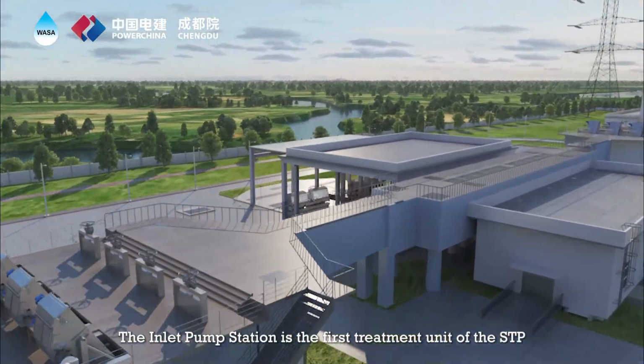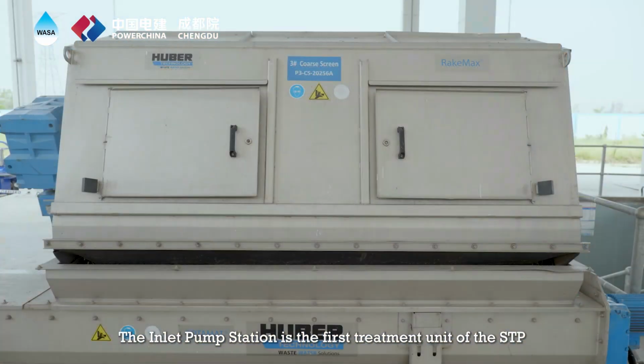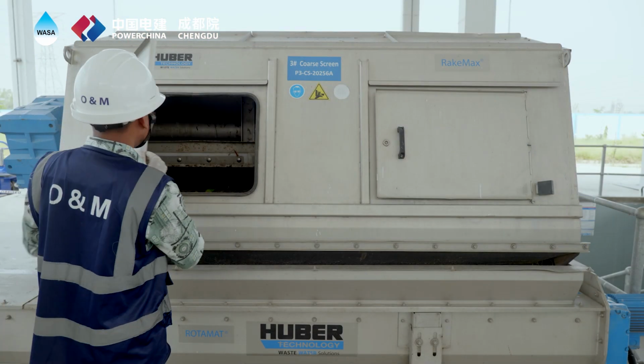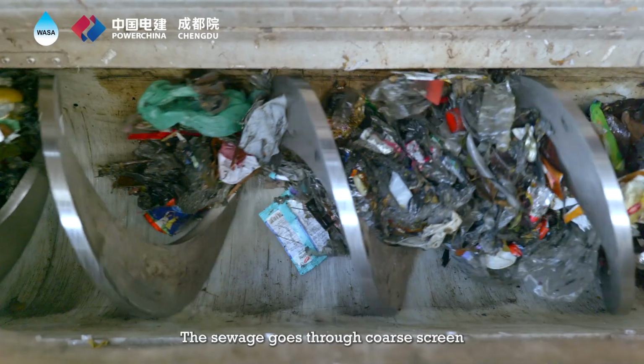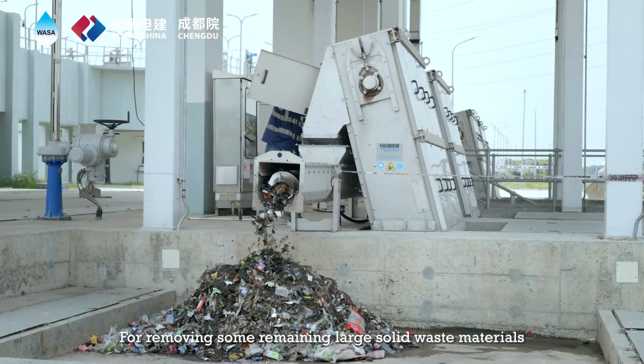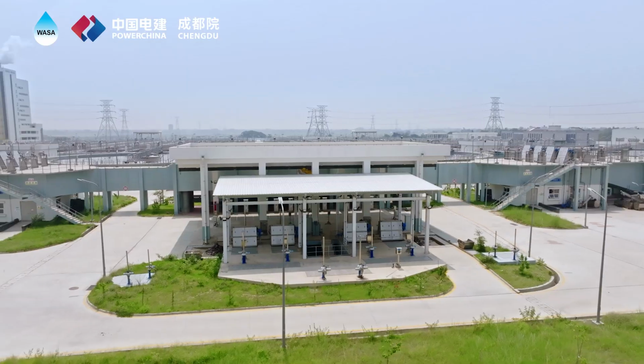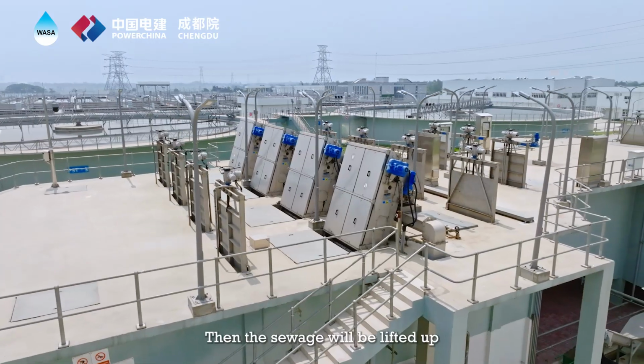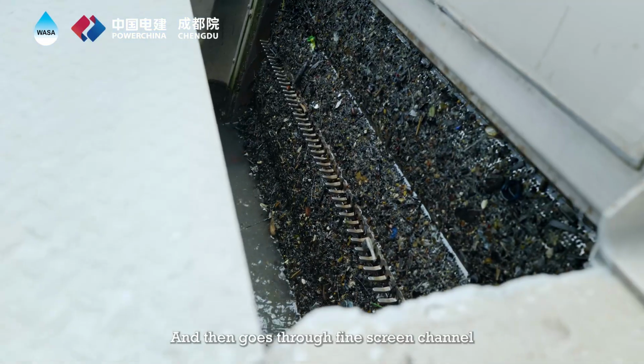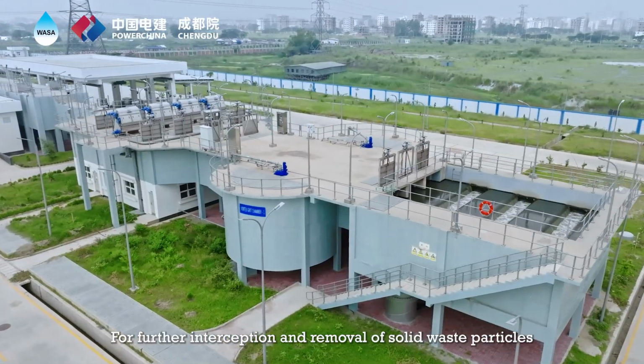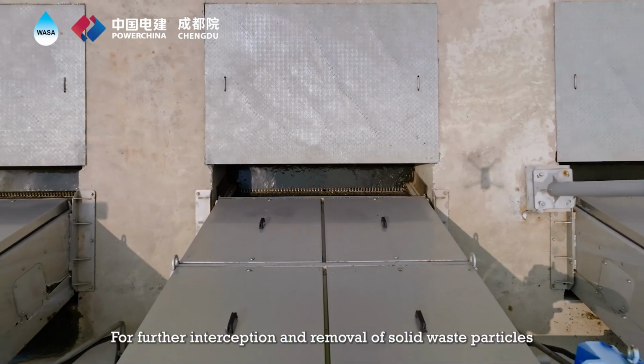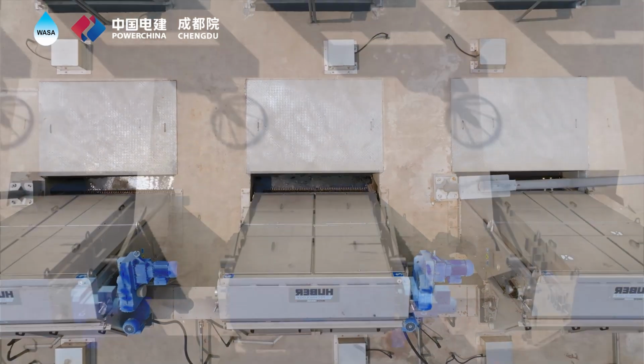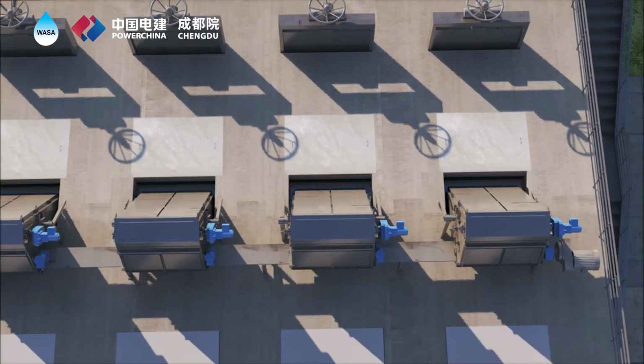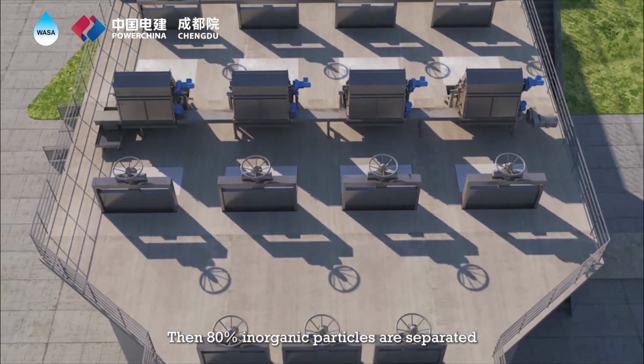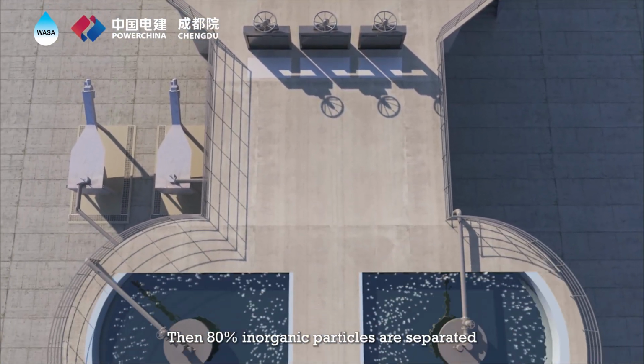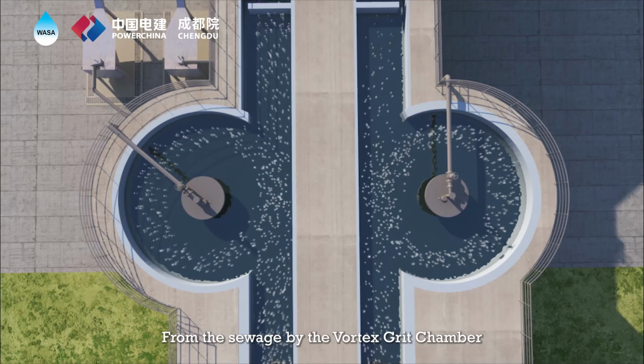The inlet pump station is the first treatment unit of the STP. The sewage goes through coarse screening for removing some remaining large solid waste materials. Then the sewage will be lifted up and goes through fine screen channel for further interception and removal of solid waste particles. Then, 80% of inorganic particles are separated from the sewage by the vortex grit chamber.